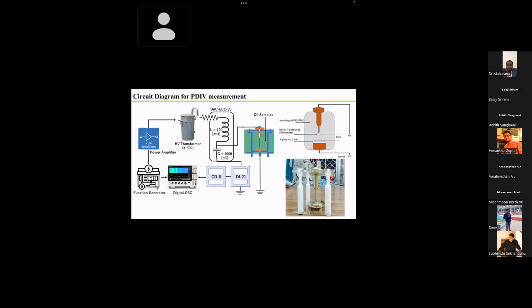So one final question: do all these problems only occur when we use paper or kraft as the interturn or winding insulation? Yes, but currently a lot of people are employing polypropylene as the interturn insulation. Polypropylene has little to no water ingress, unlike ester oil and kraft. They also have different permittivity—polypropylene is almost 2.3, while kraft is about 4.